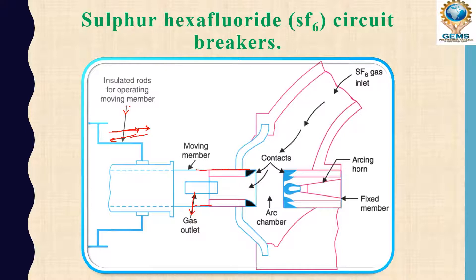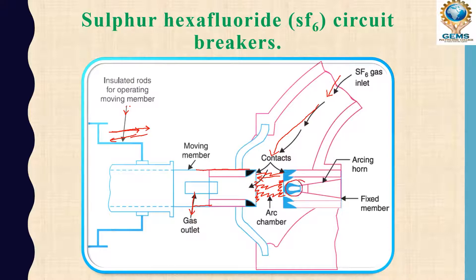This is the SF6 gas inlet. These two are the contacts - this is the fixed contact and this is the movable contact. When a fault occurs, the movable contact moves back. Then an arc is struck between the two contacts. To extinguish this arc, gas flows in from above through the inlet into the arc chamber. This is the arcing horn, which is used to control and protect against the arc.